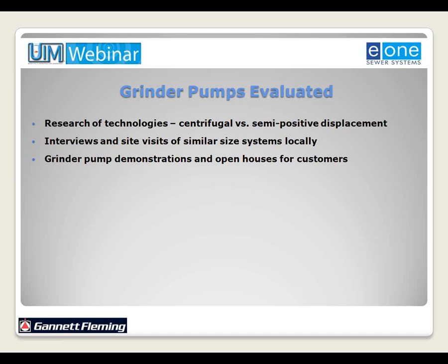Clark mentioned earlier the new E/One Extreme pump pumping against a total dynamic head of 185 feet. The Cool Spring Jackson Lake Wetonka Joint Authority pressure sewer system actually has a negative head condition, a static negative head of approximately 100 feet, and there are many pumps on this particular project that do pump downhill.